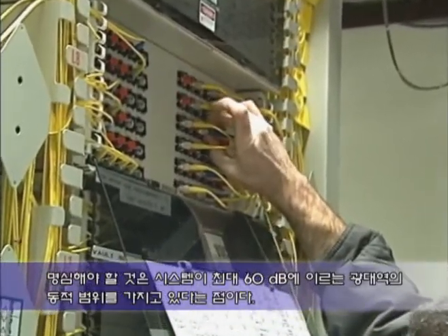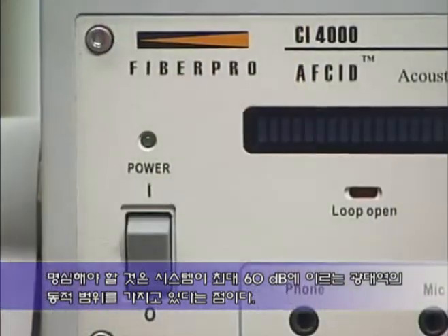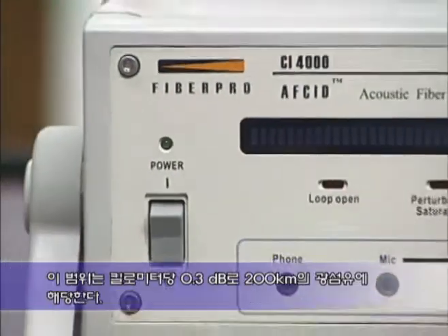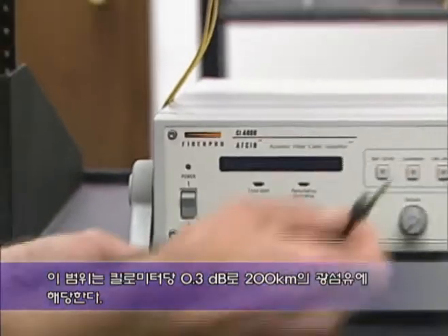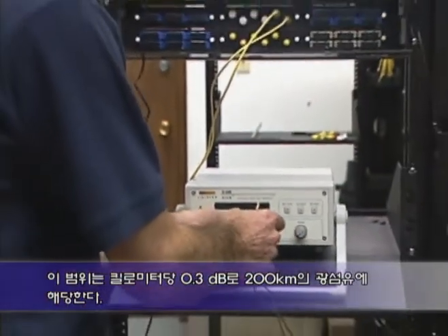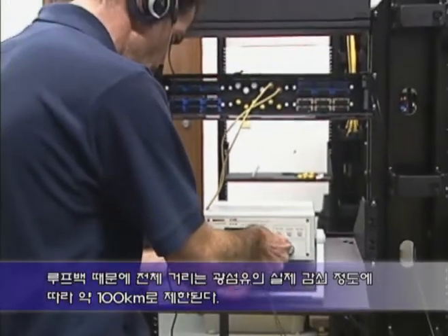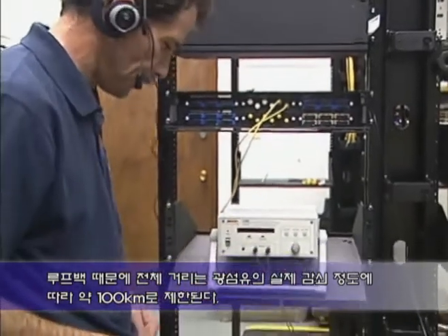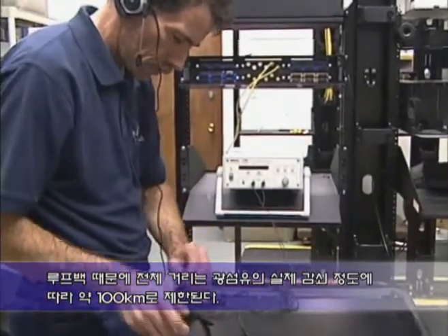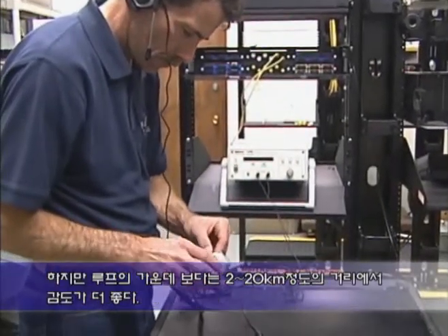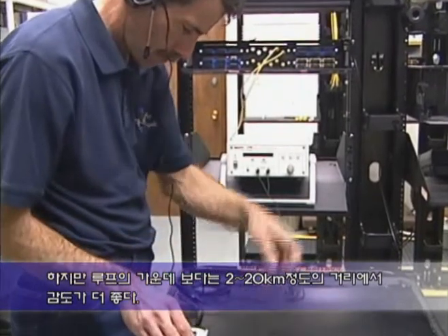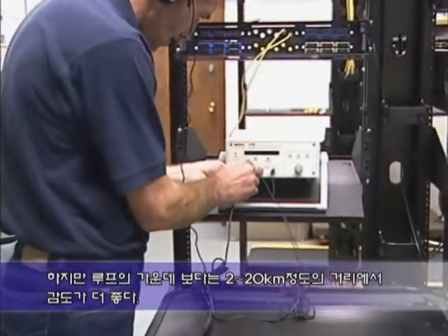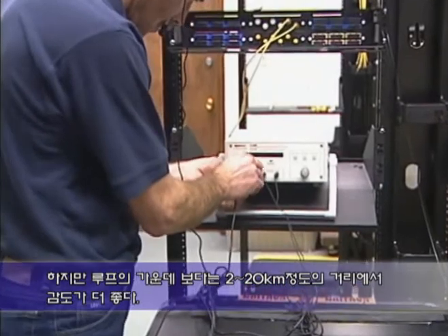Keep in mind that the instrument features a wide dynamic range of up to 60 dB, which corresponds to 200 kilometers of fiber at 0.3 dB per kilometer. Because of the loopback, total distance will be limited to about 100 kilometers depending on the actual attenuation of the fiber. However, best results are obtained when the testing occurs between 2 and 20 kilometers from the instrument.